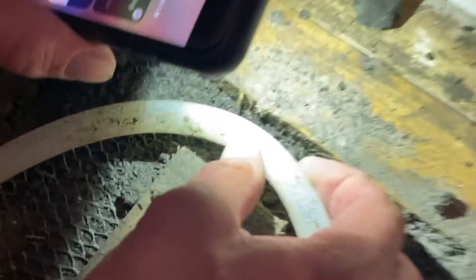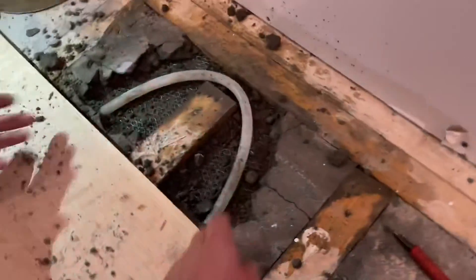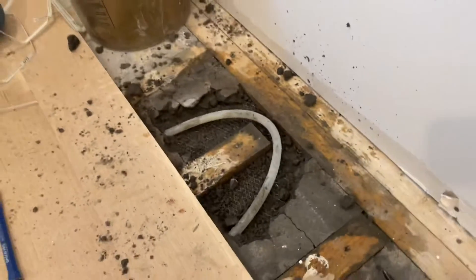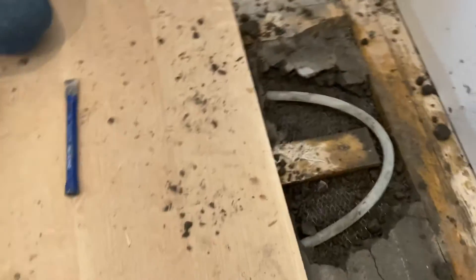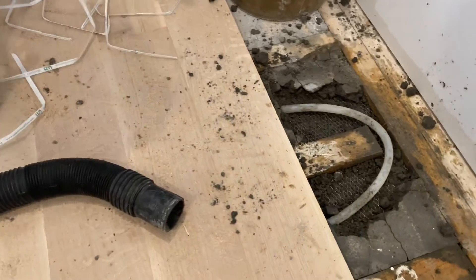That's the hole. So I think the best thing to do is to re-air it, turn it back on and pressurize it, and we'll keep an eye on that before he closes it up - to make sure it's not just spread out from what it was. We're going to have water there because it's a low point - the metal is higher. It is what it is. It'll dry out quick enough.